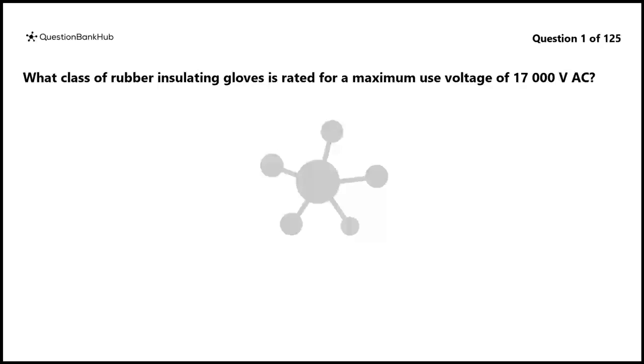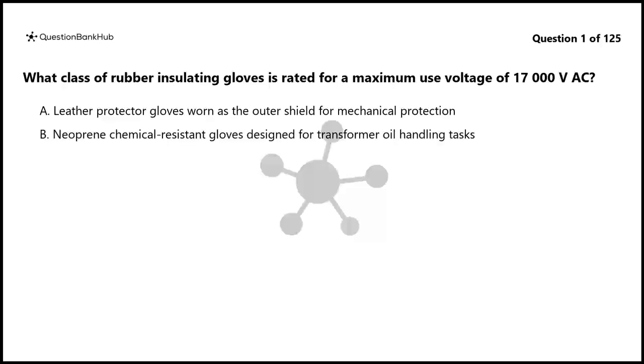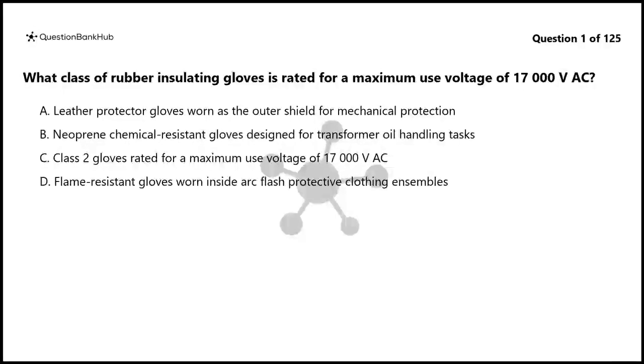Question 1. What class of rubber insulating gloves is rated for a maximum use voltage of 17,000 VAC? A. Leather protector gloves worn as the outer shield for mechanical protection. B. Neoprene chemical-resistant gloves designed for transformer oil handling tasks. C. Class 2 gloves rated for a maximum use voltage of 17,000 VAC. D. Flame-resistant gloves worn inside arc flash protective clothing ensembles.